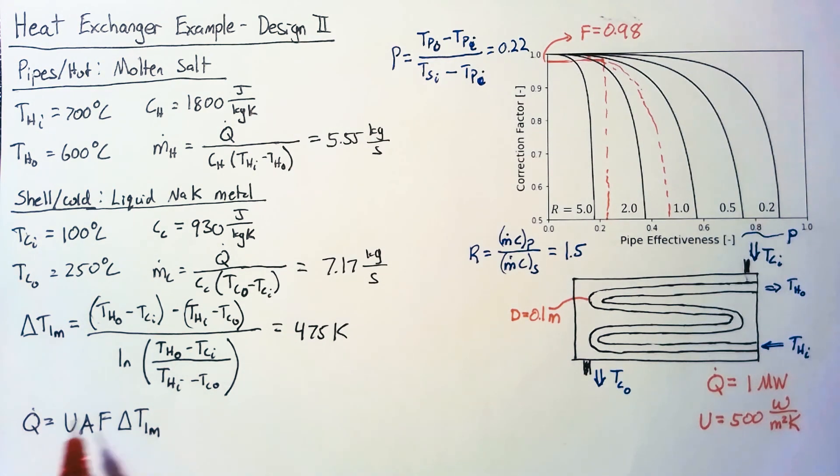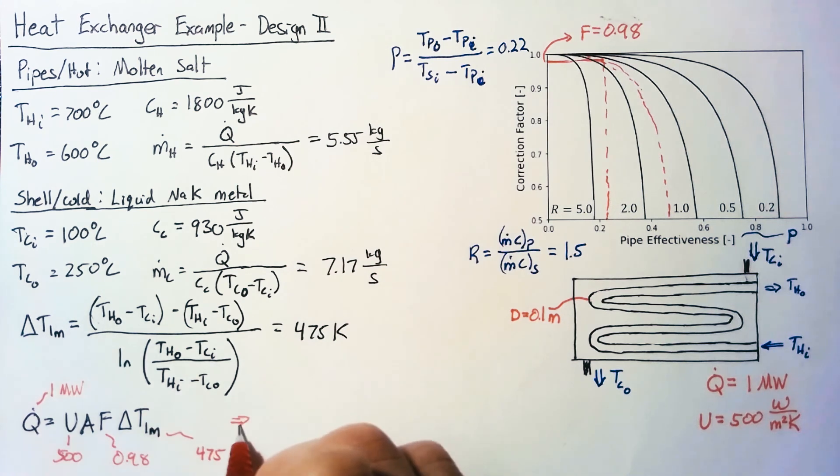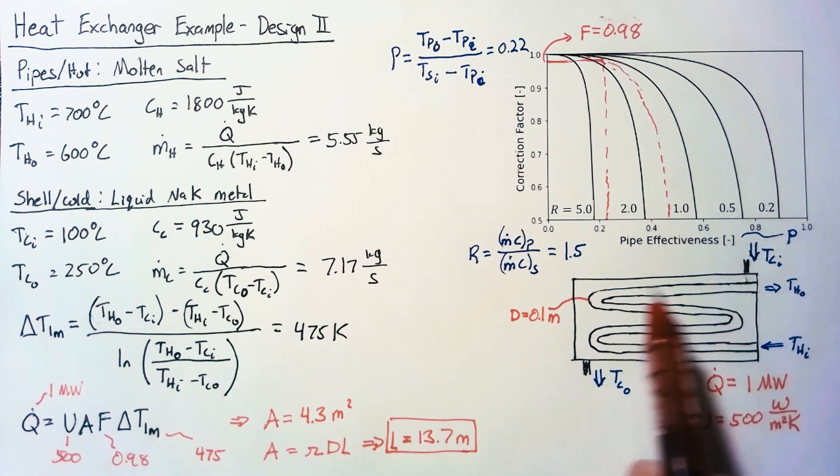So finally, we get to plug our numbers in to our Q equation. So our U was 500, our F was 0.98, our delta T was 475, and our Q dot was 1 megawatt. So that leads us to an area of 4.3 meters squared. And then, of course, we know that area is also going to be just pi times D times L for the outside of the pipe, which lets our length be 13.7 meters. So the total length of our pipe inside our shell is going to need to be 13.7 meters to match the temperatures and Q dot that we need.